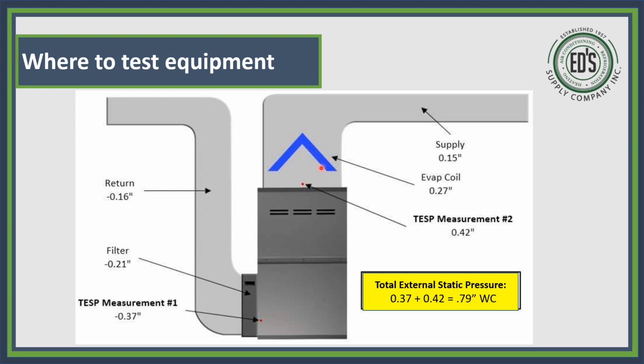This is actually a true reading of the filter, of the furnace, but I want a reading like right here, okay? But you can see what they're doing here. They did one up here in the return of the supply, and they got a 0.15. All right, they did it here, right here at the coil, and they got a 0.27, and they did it here, and it was a total of 0.42. So these two added together is the same as what you're going to get here. So you can look at this if you wanted to get real particular and see if your coil's dirty or if your coil's clean without having to tear it apart and open it and look at it on the inside. You could actually do that by static pressure. Put a probe here, see what the difference is, and you'll know real quick if that coil's dirty or not. And we'll show you how to read that. But that's going to give you a supply of 0.42.